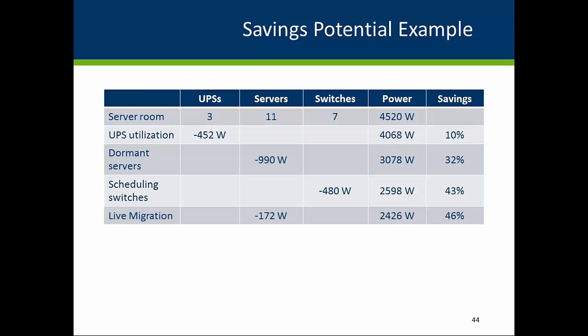Finally, if during non-office hours we migrate virtual servers to only a few physical servers, placing the remaining physical servers on standby, then assuming a 10% power savings, the total SEDC power reduction during off hours would be about 2.1 kW, or 46%. To summarize, during the work week, these measures would result in a 32% reduction in power load.